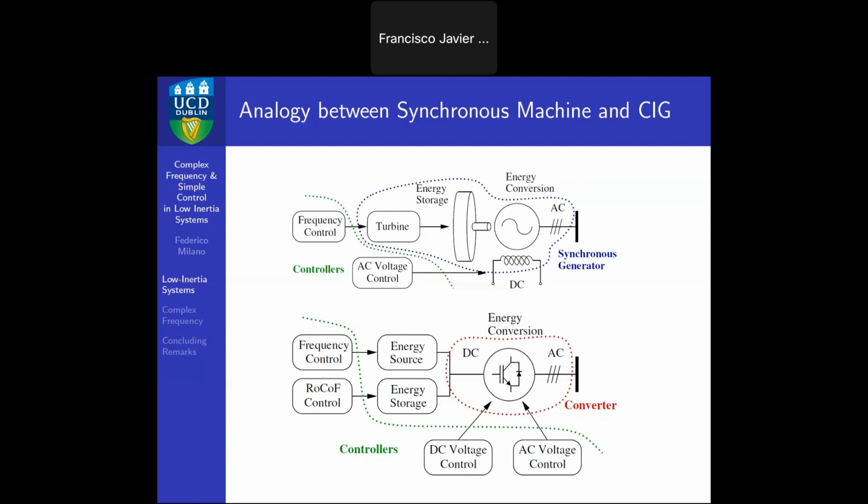Sometimes I compare this with the difference between fuses and protections. In protections, you need to design the measurement system, so the transformers, typically the relays and the breakers. In the fuse, everything is just one thing. It is the measurement, it is the breaker, it is the relay, everything in one device, right? So the machine was basically that, embedding everything inside. So we think of synchronization and the power balance as a sort of synonym sometimes, because the machines do that anyway.